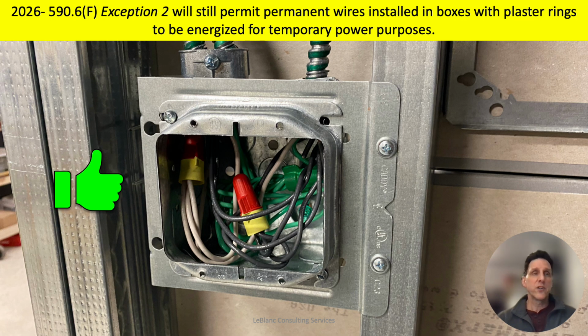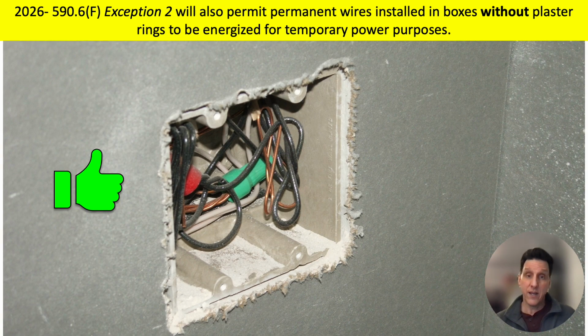Okay, so for 2026, exception 2 will still permit permanent wires installed in boxes with plaster rings to be energized for temporary power purposes. And in 2026, exception 2 will permit wires installed in boxes without plaster rings and without covers to be energized for temporary power purposes.